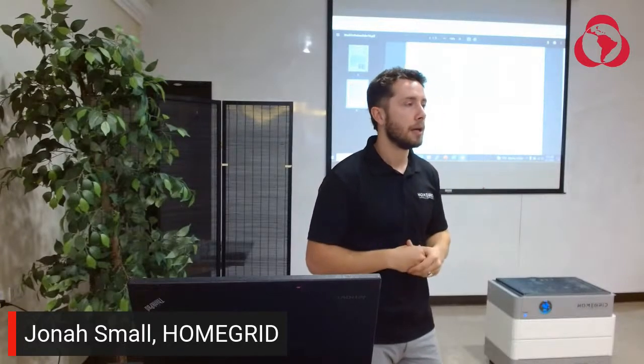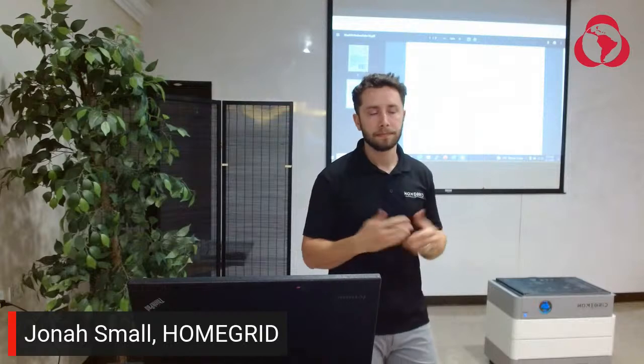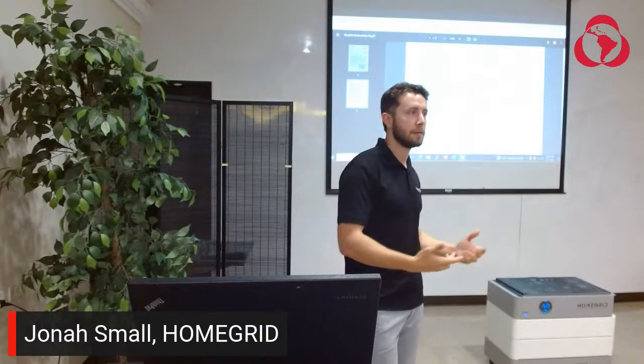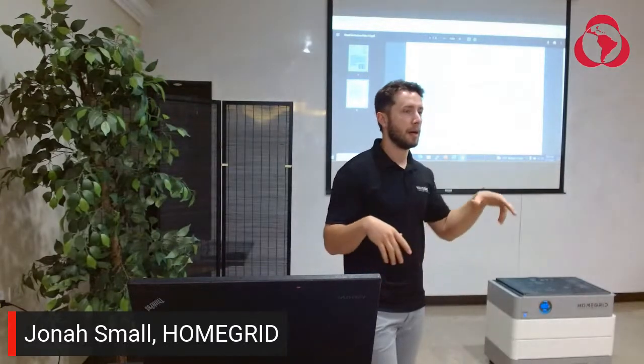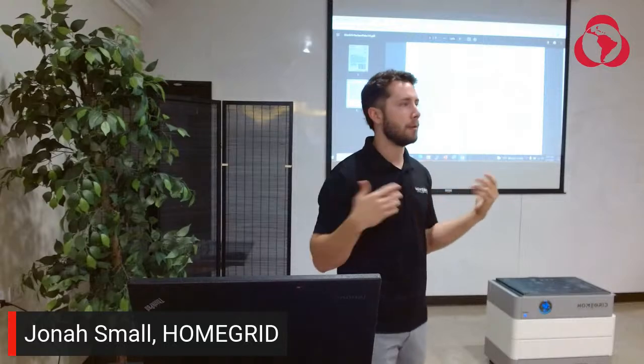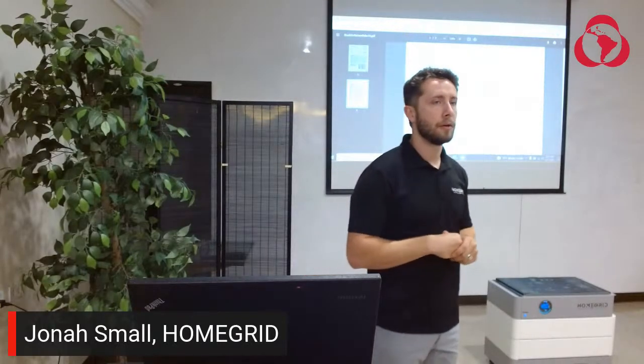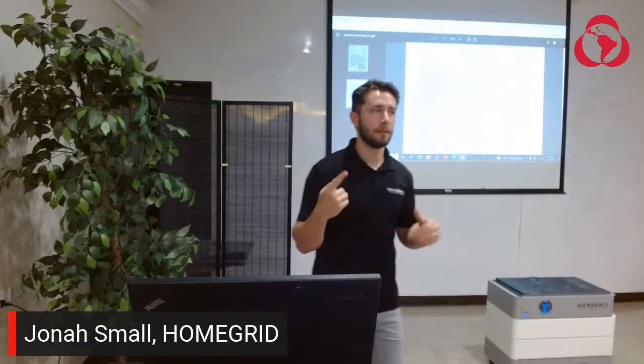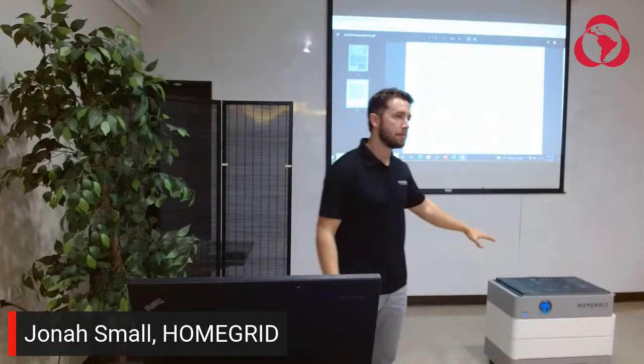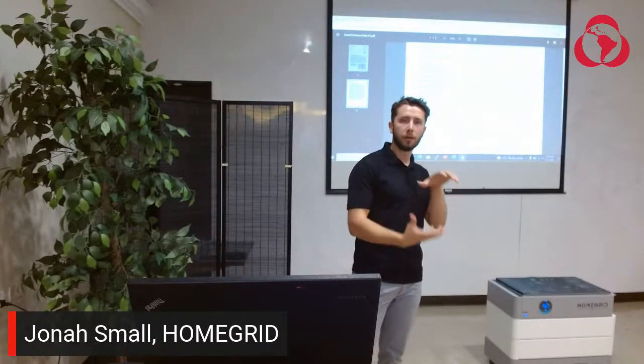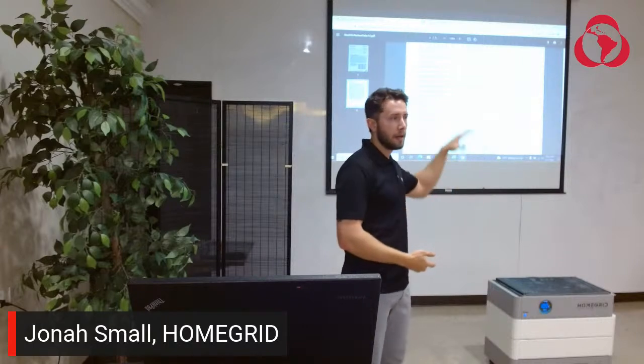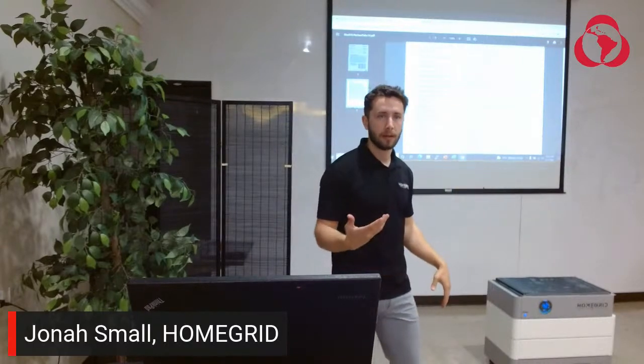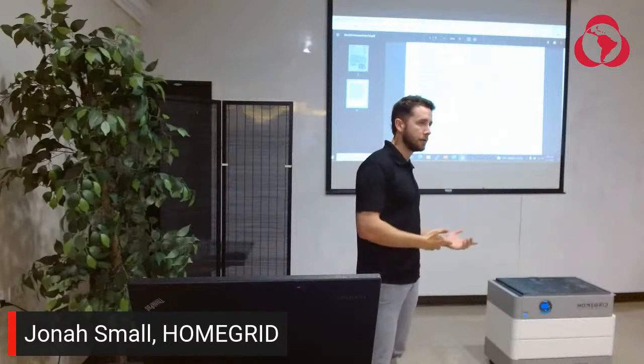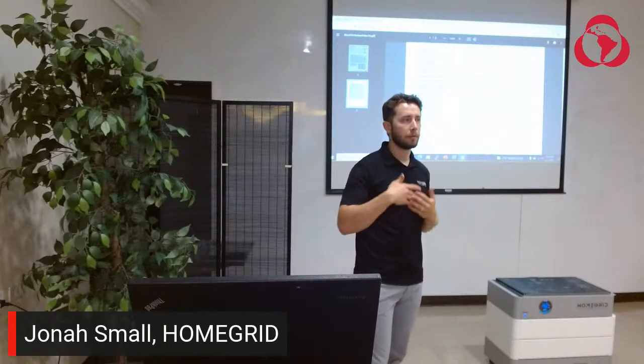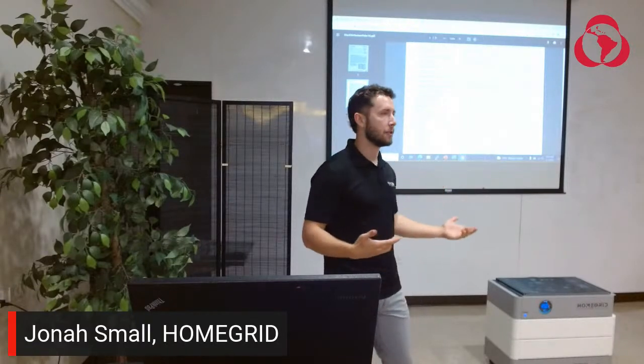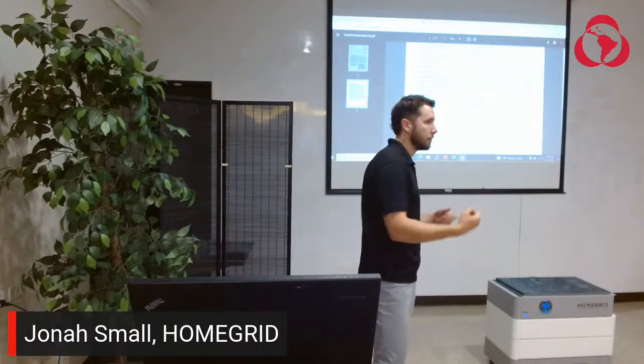We've had one module failure, and it was sad to say it was an installer's fault when he was installing the module. But we just shipped him a new one, and he shipped the old one back, no problems. That's the second benefit of the system. Because these modules are in parallel, if one of them fails, the rest of the system will continue to work. And if you need to replace a module or component, we can provide that, it takes 20 to 30 minutes to swap components because it's so easy.